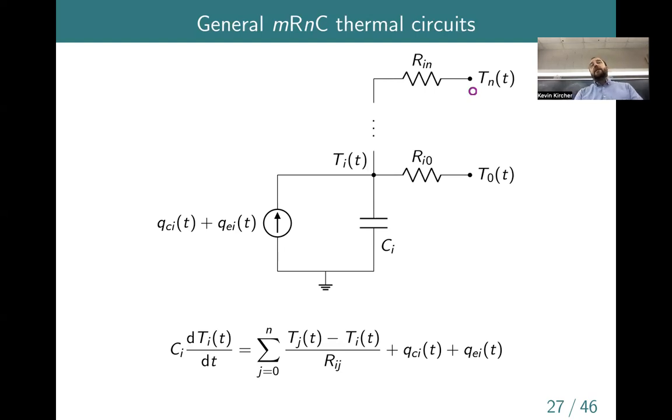Oh, there could be, yeah. So heat transfer by basically direct air flowing from one zone to another can be modeled in this network or in this kind of configuration. So typically, at least using an ideal gas assumption for the air, the heat transfer associated with mass flow of air would be m dot, the mass flow, times the specific heat of air at constant pressure, times the temperature difference between basically the input and the output air streams. So yeah, you'd have an m dot c delta T.